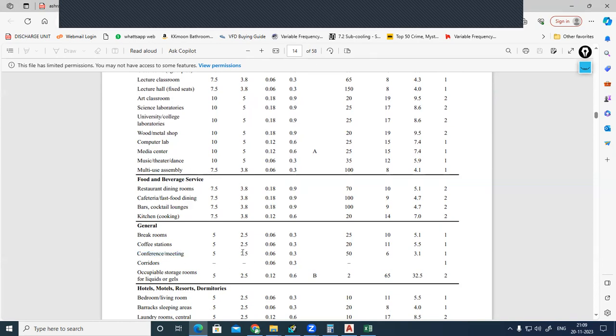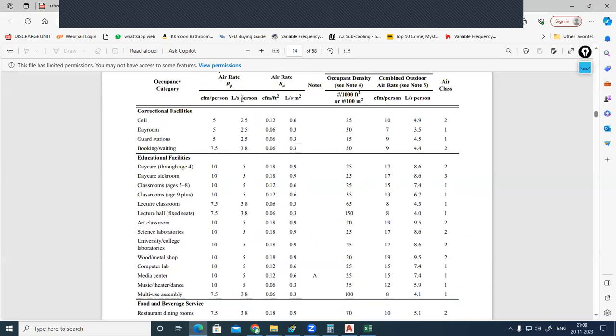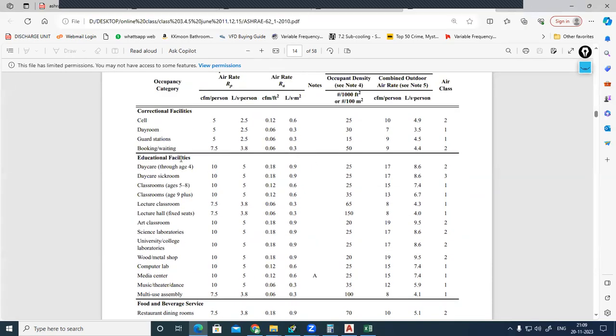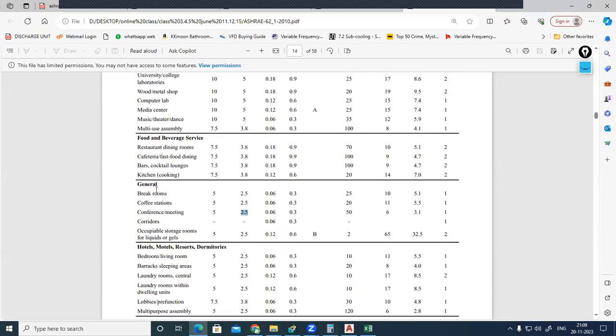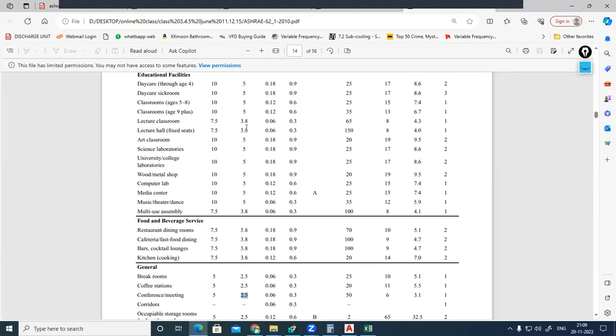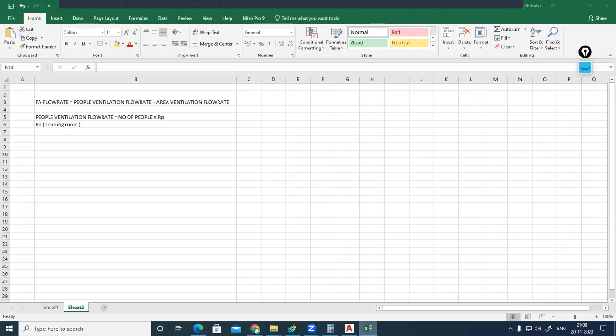How much it is, each person you should deliver 2.5 liter per second. You don't want to consider this educational facility under general conference or meeting. This one you can consider, that is fine. Even if you are considering 3.8 liter per second, that is not a big issue. Okay, but excess we don't want, right? So RP, how much we are getting? RP value, we need 2.5 liter per second per person. Liter per second per person. Each person, right? Each person we should provide 2.5.